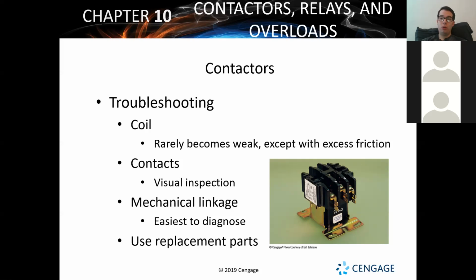If you see OL or infinity on your meter, testing from one side of the coil to the other on those two leads, it's an open coil. Somewhere in all those windings, a wire is disconnected. The other thing that can happen is a short, where the coil starts sending power somewhere other than through the coil. Part of that coil frays out and hits either the edge of the wall of the contactor, something like this metal right here. You can actually have that energized with 24 volts.